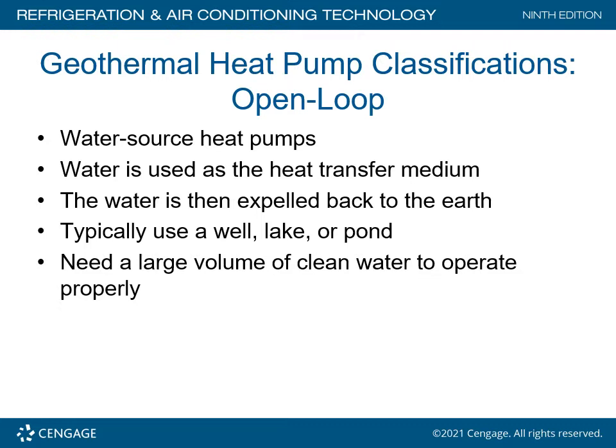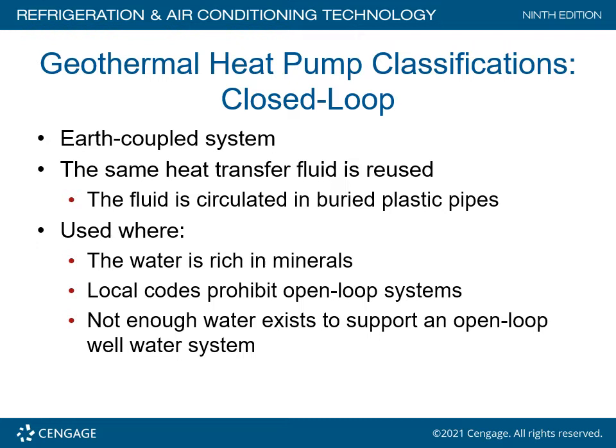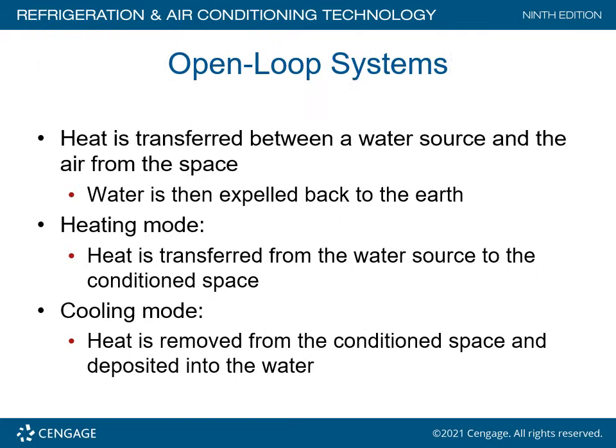Geothermal heat pump classifications. The first one would be the open loop system, which is a water source heat pump. Water is used as the heat transfer medium. The water is then expelled back to the earth. Typically used with a well, a lake, or a pond, and needs a large volume of clean water to operate properly. The closed loop system utilizes the earth-coupled system, where the same heat transfer fluid is reused. The fluid is circulated through buried plastic pipes, used where water is rich in minerals, local codes prohibit open loop systems, or not enough water exists to support an open loop well water system.